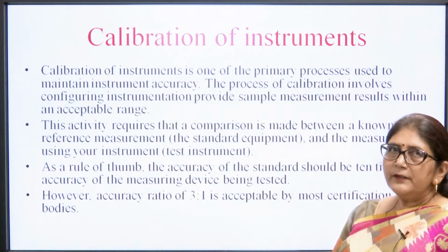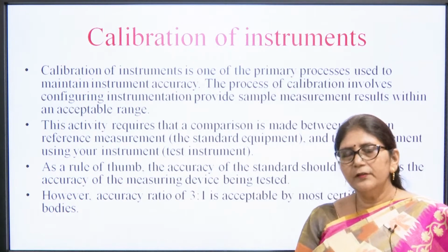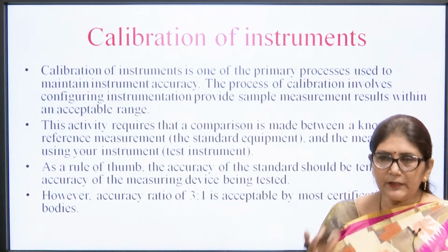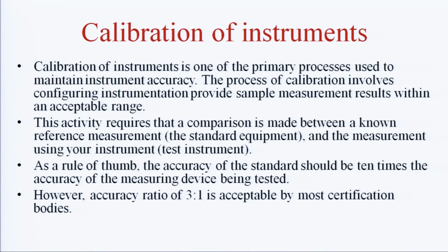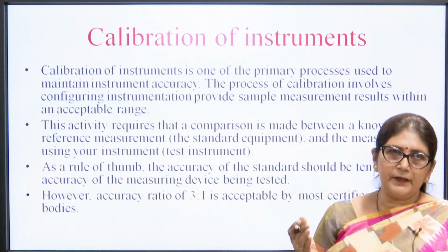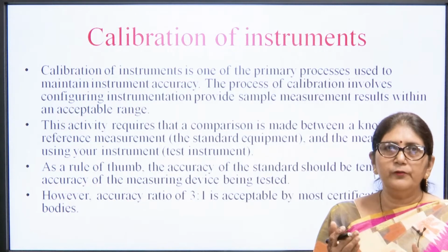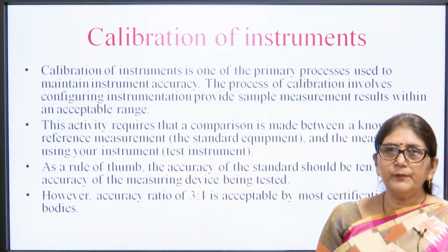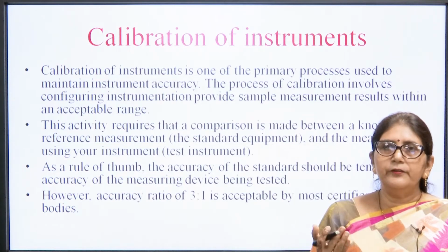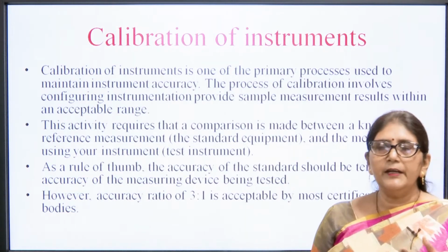Now, after the frequency meter I will discuss the calibration of the instrument. So, what is the need of calibration? Suppose we are using any multimeter or voltmeter and we are measuring the voltage or the current with that instrument. We have to assure that this instrument's accuracy is very high. Accuracy means how close the reading of the instrument is to the true value. So, we need the instrument to measure any unknown quantity very accurately. For this we need calibration.